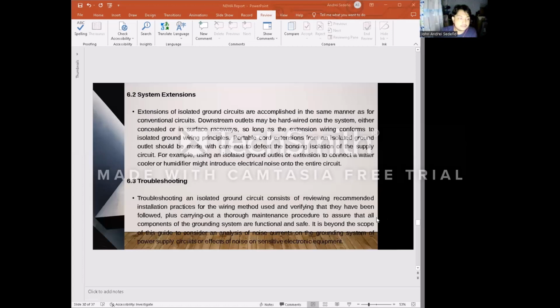Now, next is extension of isolated ground circuits, which is accomplished in the same manner as for conventional circuits. Downstream outlets may be hardwired into the system, either concealed or in surface raceways. As long as the extension wiring conforms to the isolated ground wiring principles, the portable cord extension of the isolated ground should be made not to defeat it.